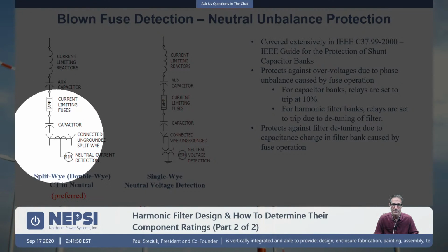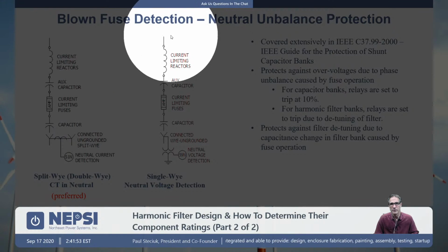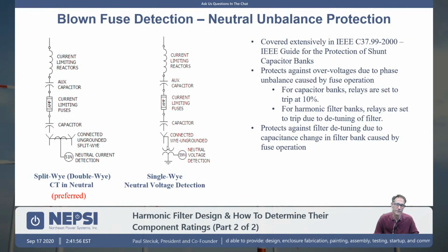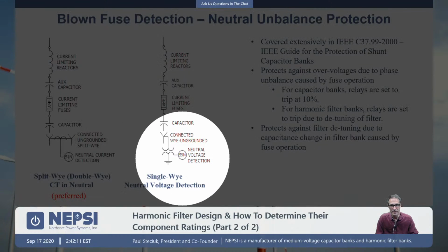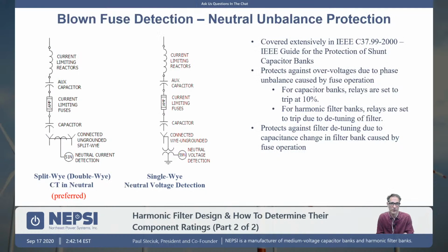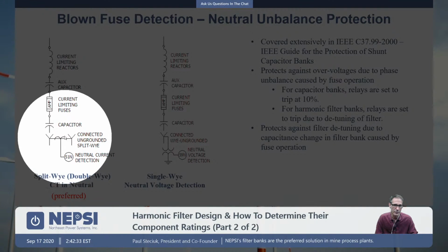We highly recommend it. And the reason, one, is in this system here, if I have an external line to ground fault, so say I'm on a distribution system and out on a feeder there's a line to ground fault, there is an automatic neutral to ground voltage shift that this relay is going to see. And if you have a line to ground fault somewhere out in a distribution system, that neutral shift could cause a false trip inside our filter bank, or inside a cap bank for that matter, if it were a cap bank. So that is one reason we prefer a Split-Wye arrangement like this. You will not get that spurious trip.